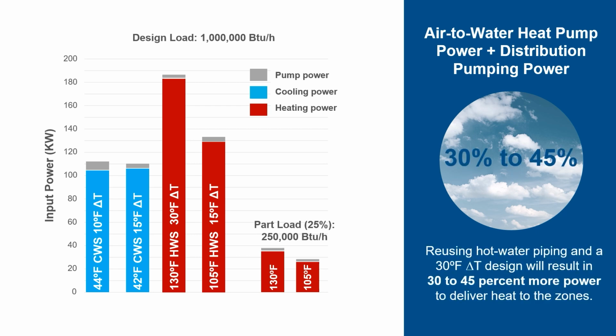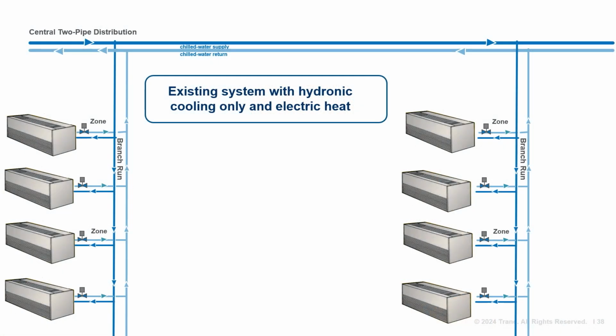Overall, for fan coil systems, if you're constrained to reuse existing hot water piping in a 30-degree delta T, this will result in 30 to 45% more power to deliver the heat to the zones. So there is a substantial energy and power benefit of using area switchover in coils that are sized for both heating and cooling. Let's look at another scenario.